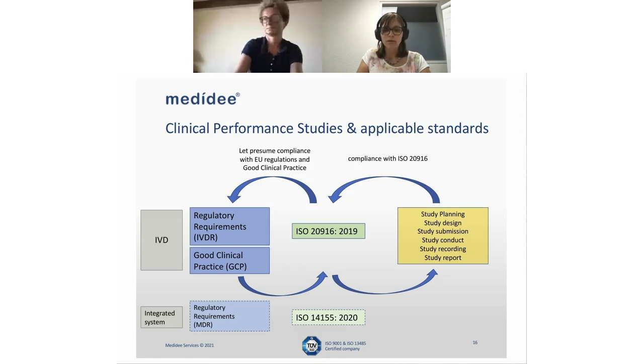Now, whenever you plan, you design, you submit, you conduct, you record, and you report a study, and you do it in compliance with this ISO 20916 standard, this will allow you to presume compliance as well towards the regulation and the good clinical practice.